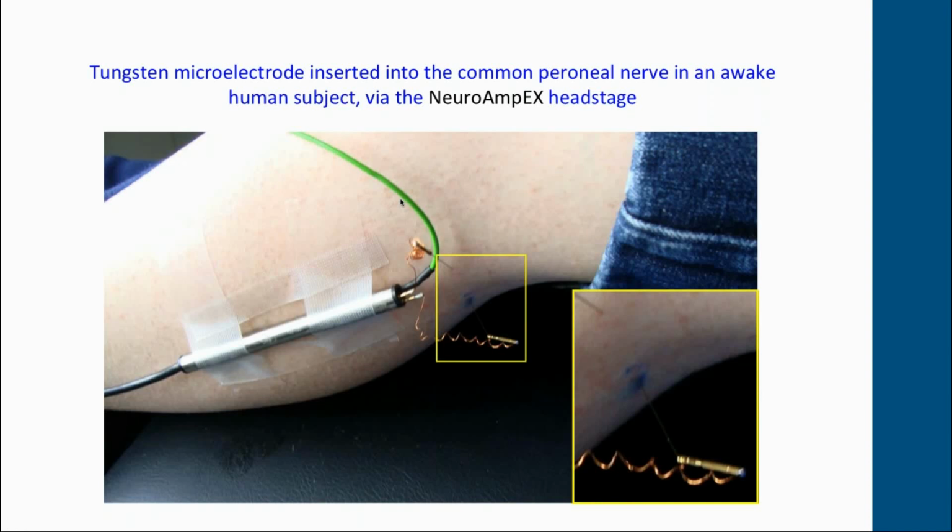Typically we will use a microelectrode that has gone through several cycles of use. Once its impedance becomes very low, we just use it as a reference electrode. We will scrape about 1 millimeter off the tip, clean it and re-sterilize it. Now, some of you, your human ethics committees or institutional review boards may not allow microelectrodes to be reused, re-sterilized, which I think is crazy. In which case you can buy reference electrodes, so just bare reference electrodes from FHC.